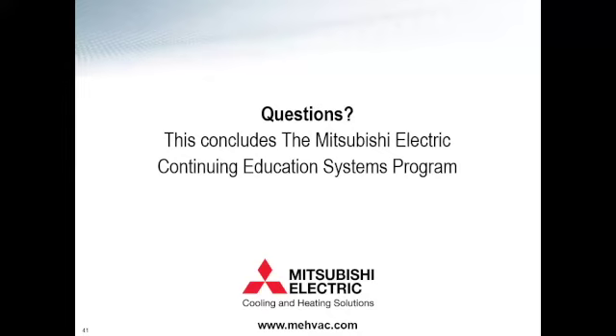Yeah. There were quite a number of questions about refrigerant. The phase out of R410A, somebody said that R32 looks like it's the next one. I forget what the R is for carbon dioxide. Because it is a problem that leaks in refrigerant piping are probably void a lot of the efficiency gains, which somebody was noting in this. So maybe speak a little about that and whether you're looking at other forms of other media, like in supermarket installations for their coolers, that they're actually using some form of antifreeze, a liquid, as opposed to refrigerant. So whether, for these larger applications, what you guys are thinking about and what you offer now. Absolutely. So Mitsubishi is always forward looking and thinking about things like this.